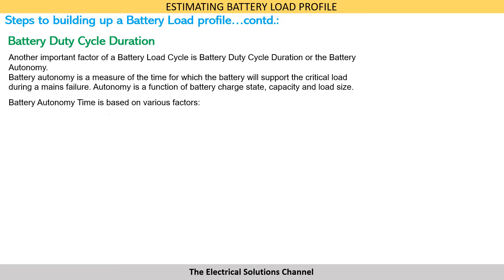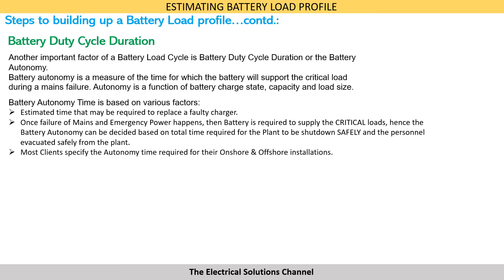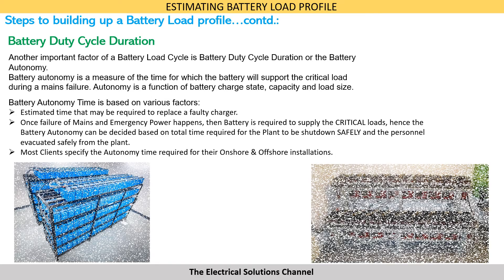Battery autonomy time can be decided based on various factors — for example, the estimated time required to replace a faulty charger, or the total time required for the plant to be shut down safely and personnel evacuated safely from the plant after failure of mains and emergency power. Most clients specify the battery autonomy time required for their onshore and offshore installations.